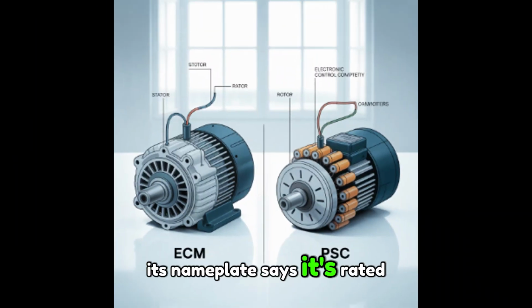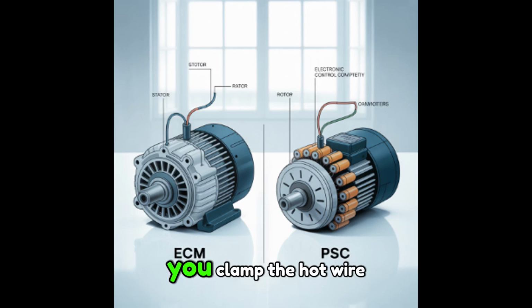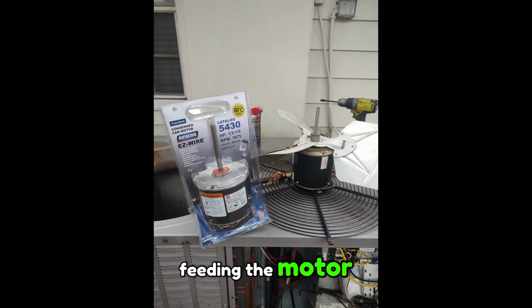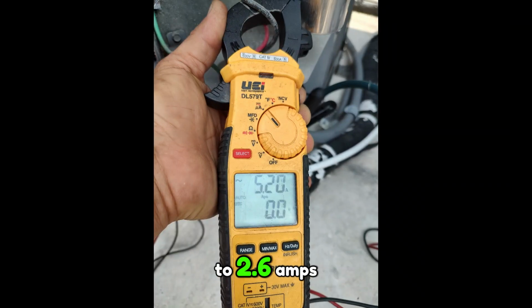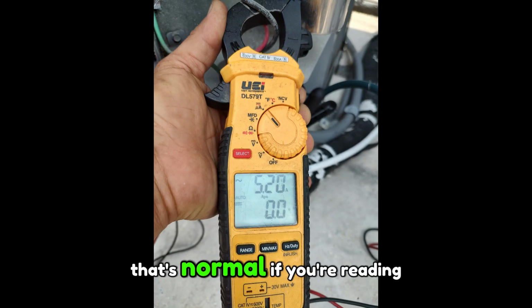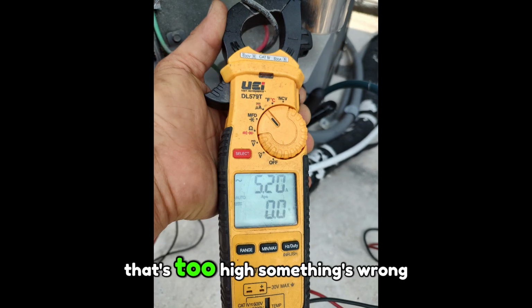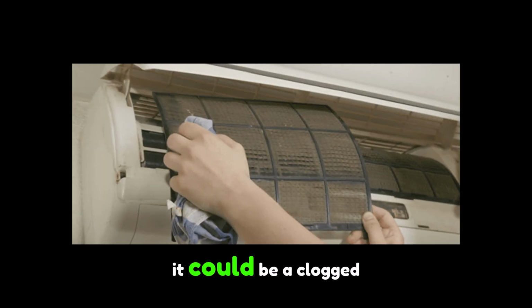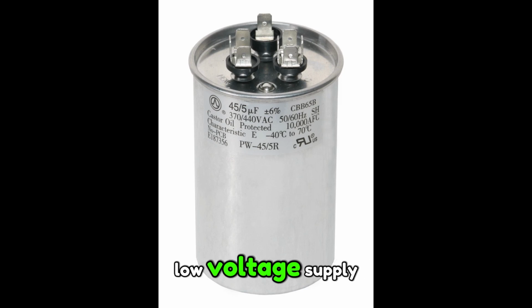Example, you're checking a blower motor. Its nameplate says it's rated at 2.5 amps. You clamp the hot wire feeding the motor. If your reading is 2.4 to 2.6 amps, that's normal. If your reading is 4 amps, that's too high. Something's wrong. It could be a clogged filter, a bad capacitor, or even low voltage supply.